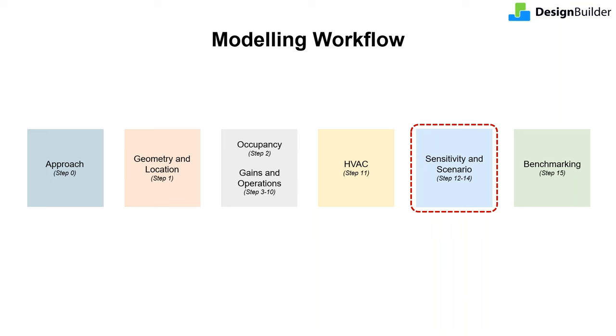Now moving on to the next part: presentation of results that account for uncertainty. After the initial baseline projection, sensitivity analysis and scenario testing should be done at appropriate stages to understand the factors that are likely to have the greatest impact on the end energy consumption of the building, presenting the results as a range. For that, you would normally define — via interviews with stakeholders — the key parameters that might vary between the design and operation stages, such as HVAC system specifications, operation protocols, and occupancy patterns.